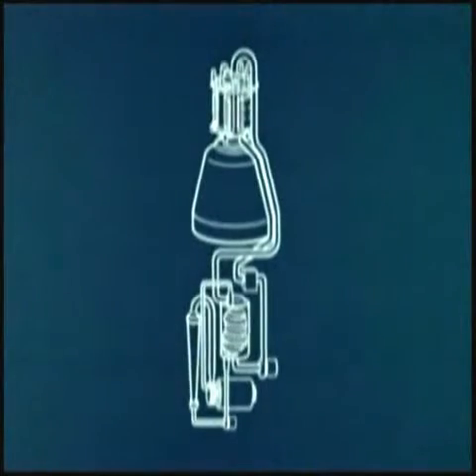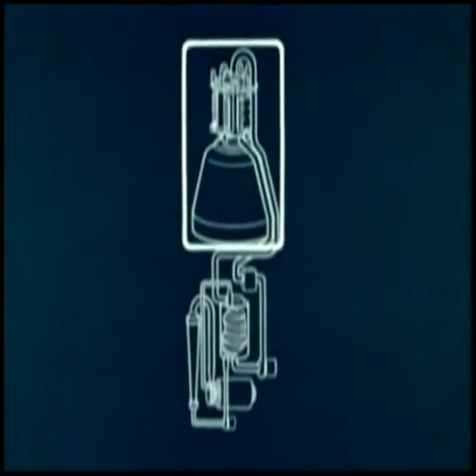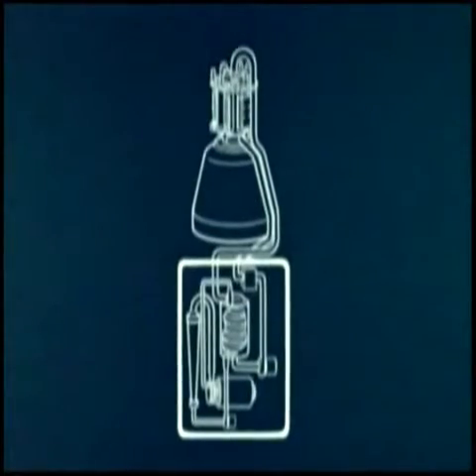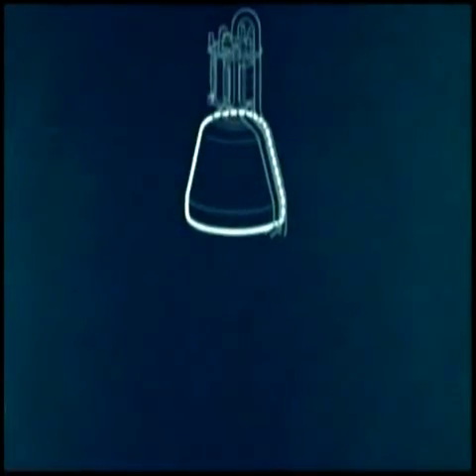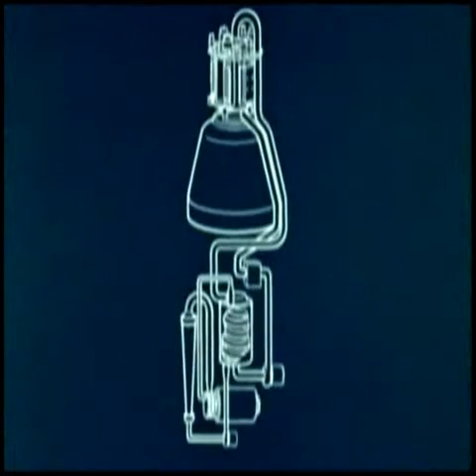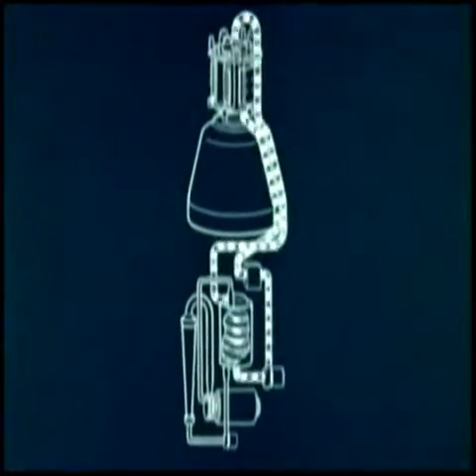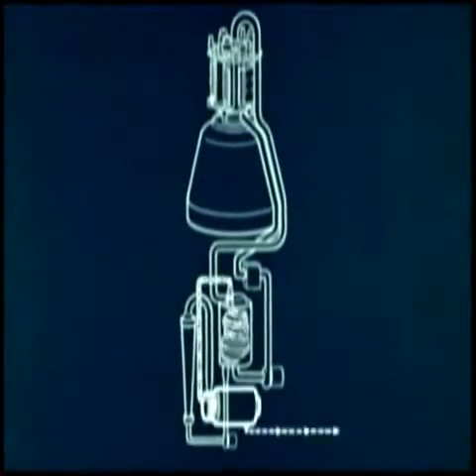The entire SNAP-8 electrical generating system is comprised of the nuclear system and the power conversion system. The nuclear system consists of the reactor core structure, controls, safety devices, and shield. The reactor heat is transferred to a mercury boiler through a closed-loop NaK coolant system. The resulting mercury vapor drives a turboalternator, which generates 35 kilowatts of net electric power.